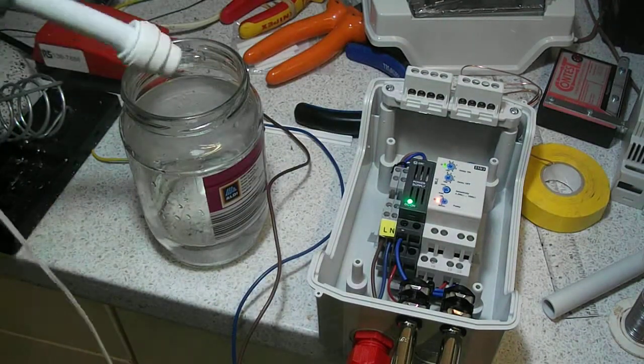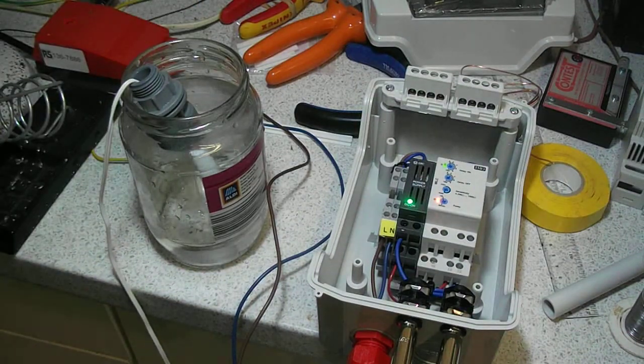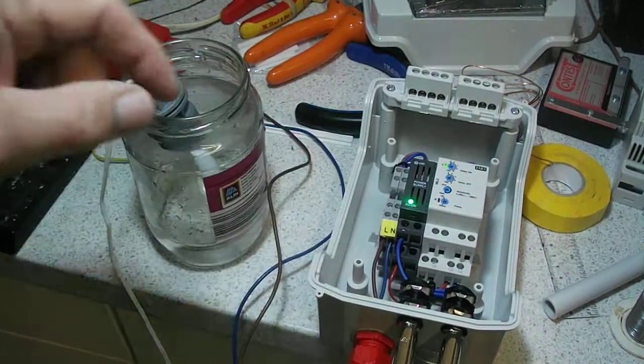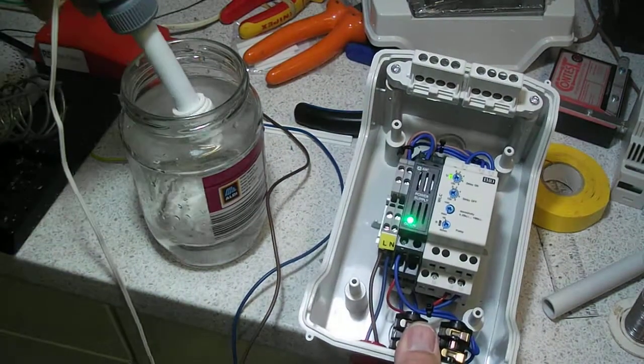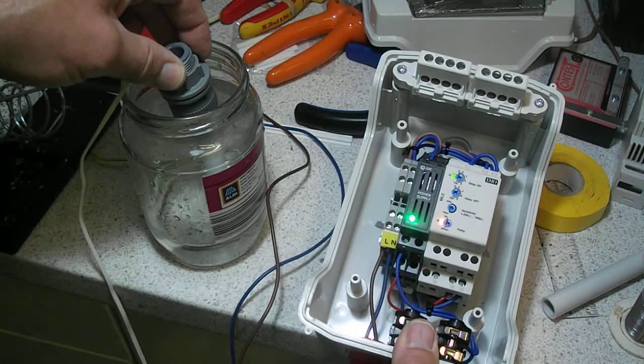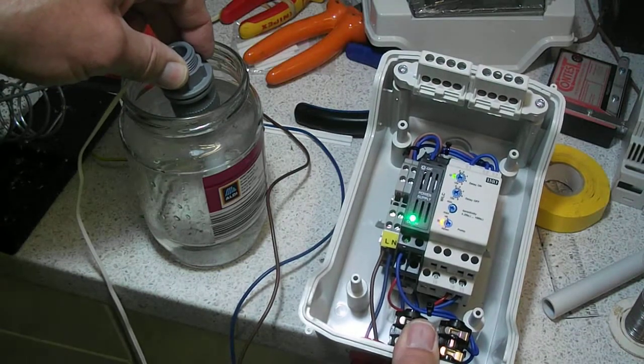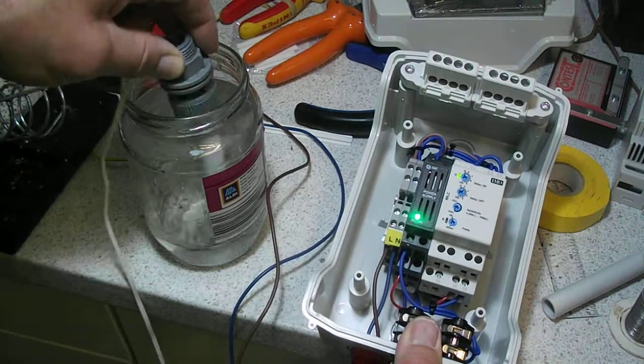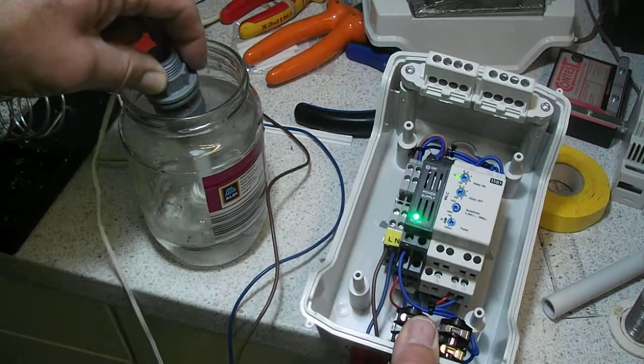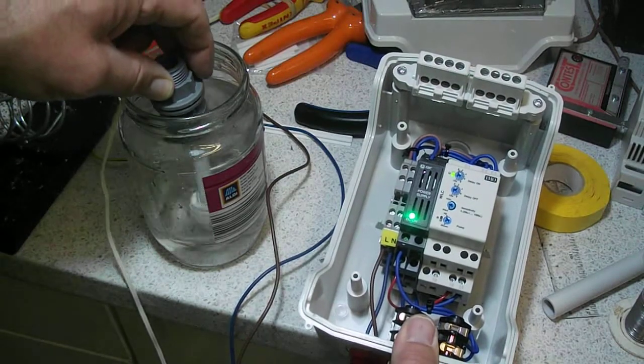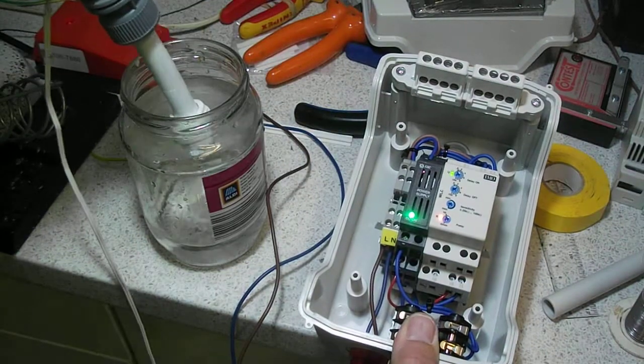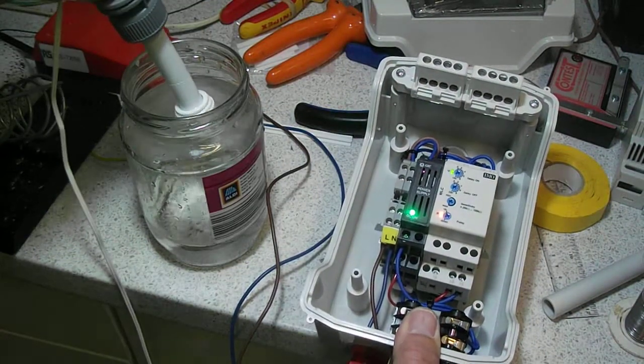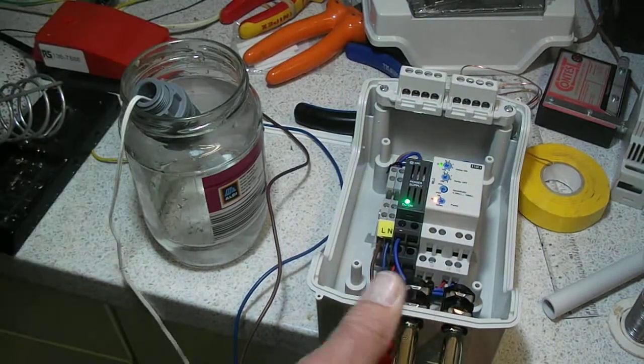So when it dips into the water, there's a few seconds delay and it goes off. Take it out, a little bit of delay, and it goes off. This is useful because if there are waves in the tank, it smooths those waves out and saves intermittent operation of the solenoid valve.